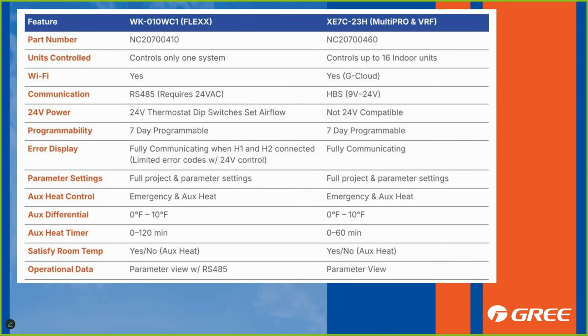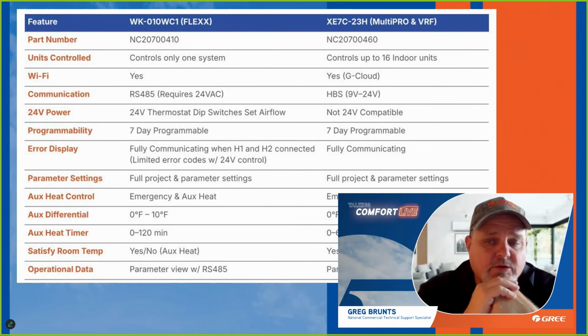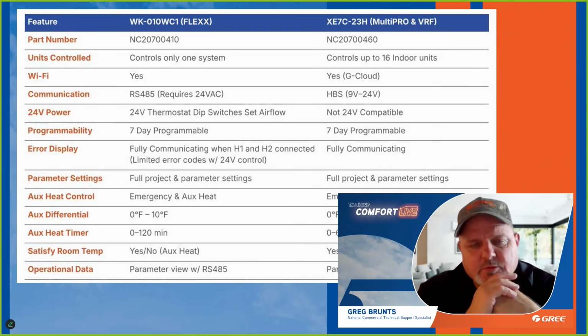If you are not using that wired controller, if you're just using strictly 24-volt control, it will give you error codes, but those error codes will display on the outdoor or indoor unit, on the boards themselves. So it would take you guys taking the panels off to go see what that is. Well, the controller would still be able to give you the error code, provided you hook up the L terminal, like a mitigation alarm, stuff like that. They give you some of the error codes. It's going to be limited though. Right. It can't give me any outdoor error codes because it's not communicating to the outdoor unit. And you're going to get limited error codes from the indoor unit in the 24-volt setup. Yeah, I got what you're saying.